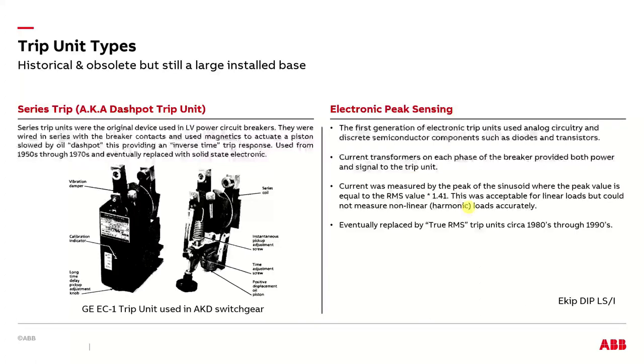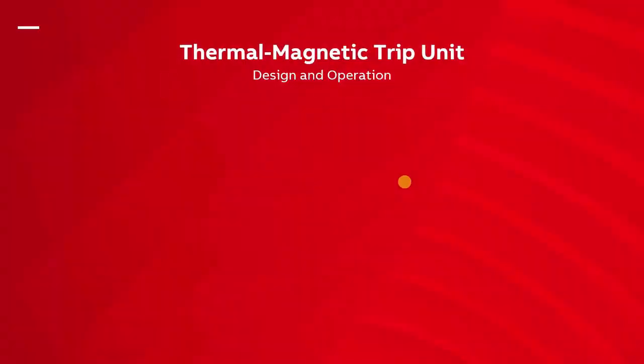And then the first generation of the solid state trip unit were these analog electronic circuit boards. They used resistors and diodes and transistors, and they were really simple. They're an improvement, but one of the disadvantages is that the electronics were so simple that they really couldn't measure RMS values. So they were peak sensing, and that caused some difficulty in the industry for a couple of years. They lived around the 80s through maybe the mid 90s. And I don't think anybody still manufactures breakers like that. So you'll probably see these out there, and you'll probably have to coordinate to them because they may be existing and they're not going to replace it.